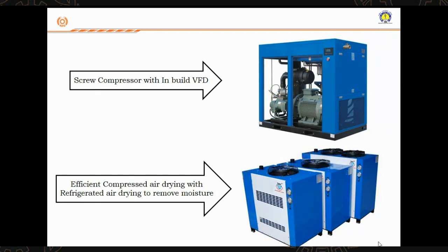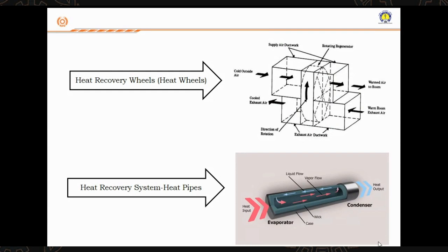But this technology is available in the market. And you know that you have a compressed air system where you use the compressed air for your plant operation, and also for your instrumentation air requirement. The instrumentation air needs to be dried, because there will be some amount of moisture, and that moisture needs to be removed. If you would like to remove that moisture, we have a new breed of refrigerant air drying systems, which are more efficient compared to the normal absorption moisture removal. Now you have these heat recovery wheels.